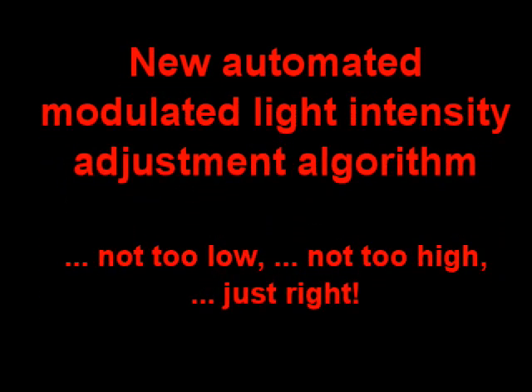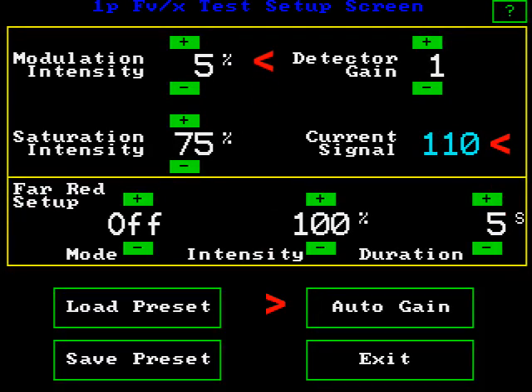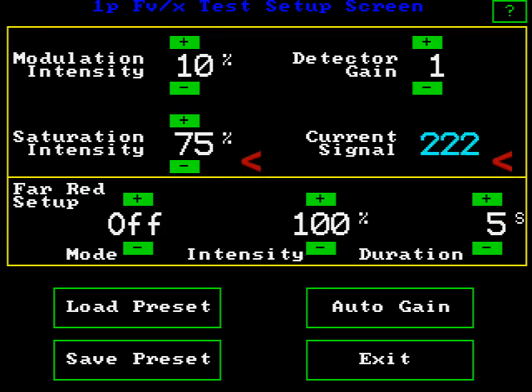To get reliable measurements, FO or minimum fluorescence must be measured reliably. To do this, the modulated light source must be set high enough to detect minimum antenna fluorescence, but not high enough to drive photosynthesis. Improperly set modulated light sources can be a source of measuring error. To overcome this, the OS-1P offers a special new routine that sets the modulated light source correctly and automatically. While old-school researchers can still set the modulated intensity manually, this new and unique option should prevent improper adjustment and provide more reliable measuring results.